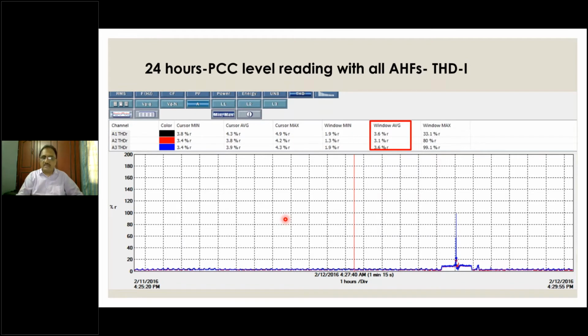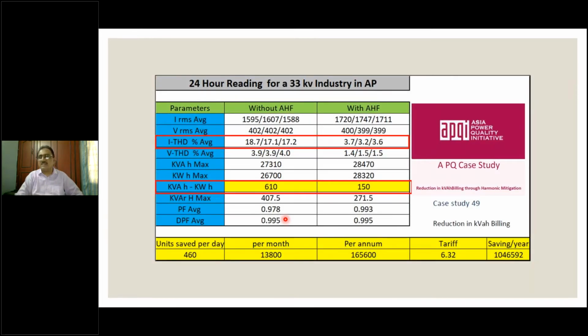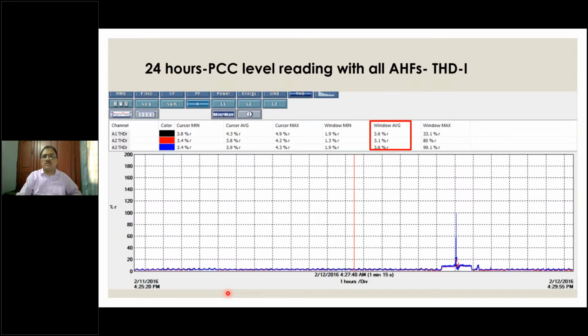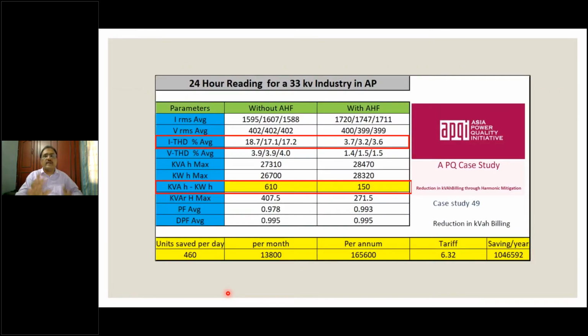So once we achieved this, we wanted to educate the customer as to what is the cost benefit. I have written this particular case as case study number 49 under APQI, Asia Power Quality Initiative, in which I am a member. Reduction in kVAH billing through harmonic mitigation. I could have used the same 24-hour window to show you what is the kVAH, but then I thought I will quickly come to the conclusion of this. So this was in one time when we did the audit, 18.7, 17.1 and 17.2 current harmonic, brought down to 3.7, 3.2 and 3.6.